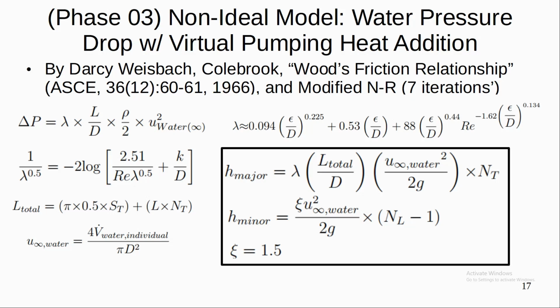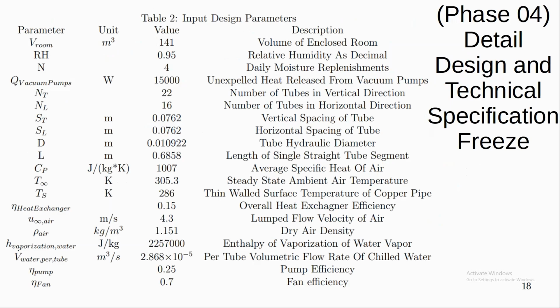I used Darcy-Weisbach, the Colebrook friction factor equation, and then something called the Woods explicit friction relationship for all of the conceptual design. But I sat down and properly wrote a Newton-Raphson subroutine that solved the Colebrook equation a little bit later, but it never performed quite as quickly. And this equation is almost uniformly a 5% more conservative calculation than even the actual Newton-Raphson, so it was a pretty good initial approximation. Without further ado, here's most of the technical data that inputs into the model.